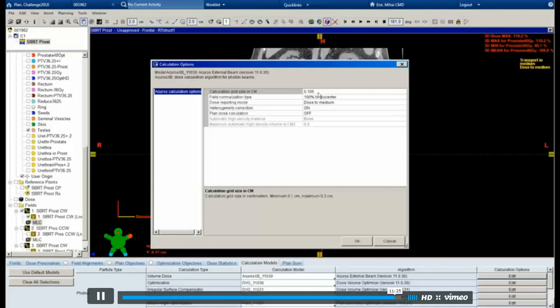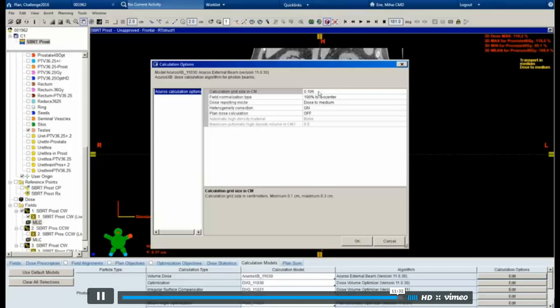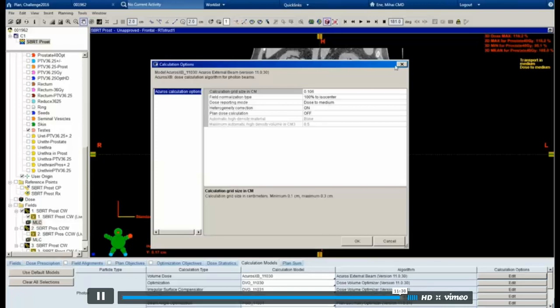I changed my grid size to 1.0 something or 1.1, and then I just made my calculation boxes as small as possible. So the grid was 1.06. And that gave you enough to get in there. Yeah. And then, of course, the smaller the calculation grid size, the more my numbers agreed with ProKnow's numbers, because I noticed when I used the bigger grid size, I was a little off.